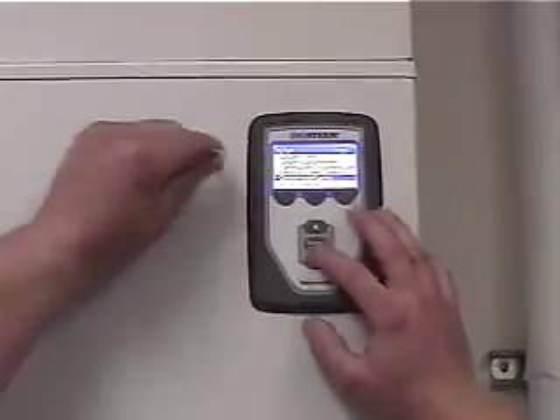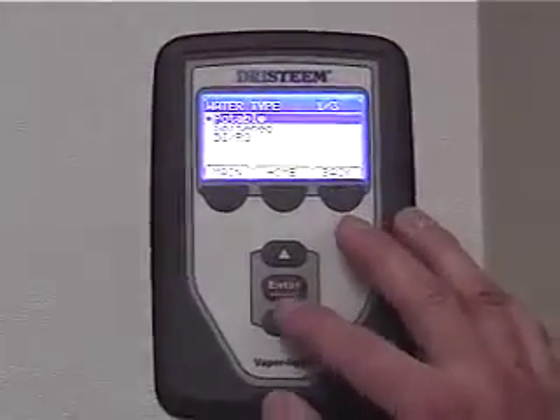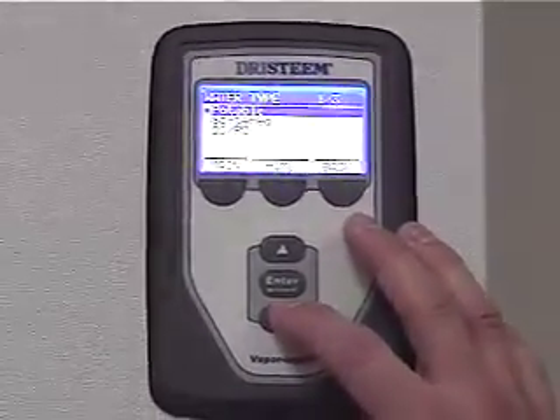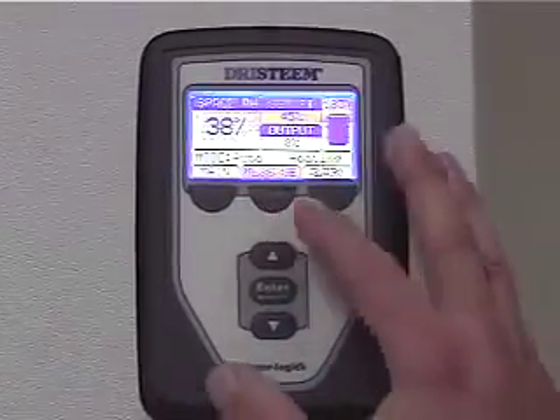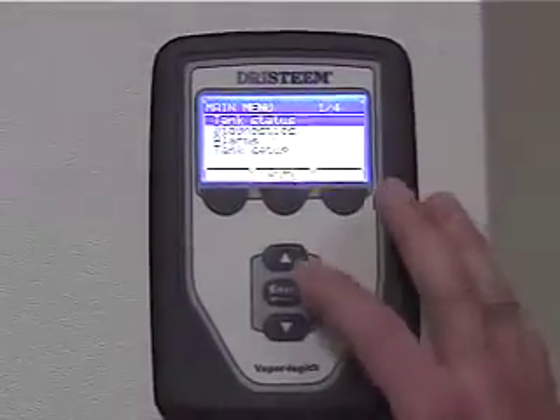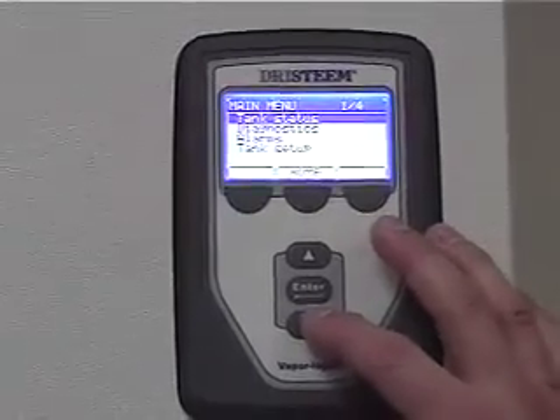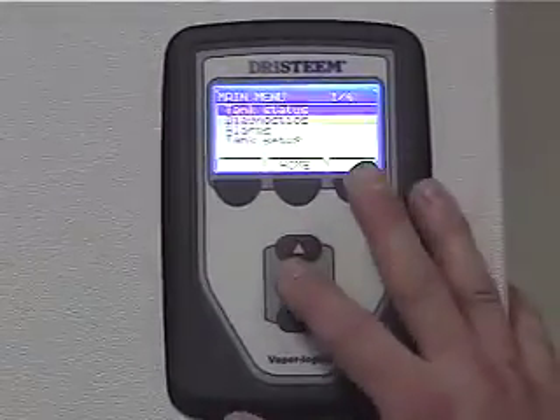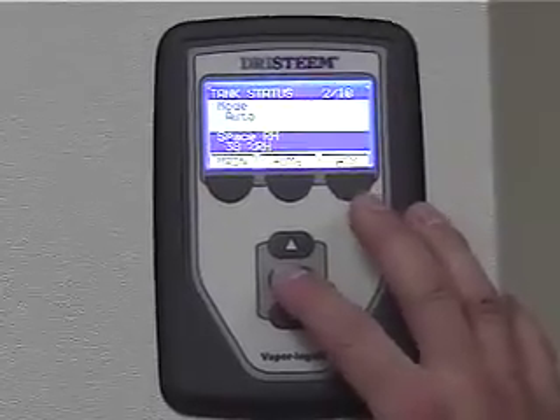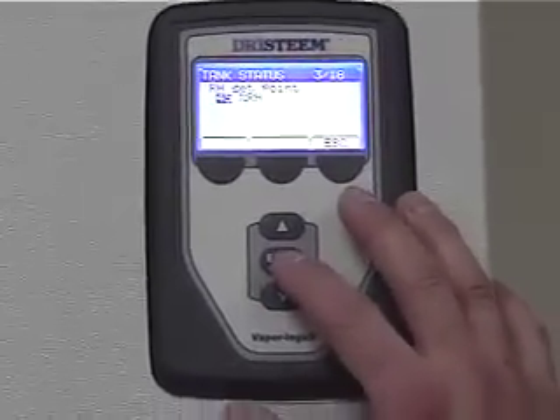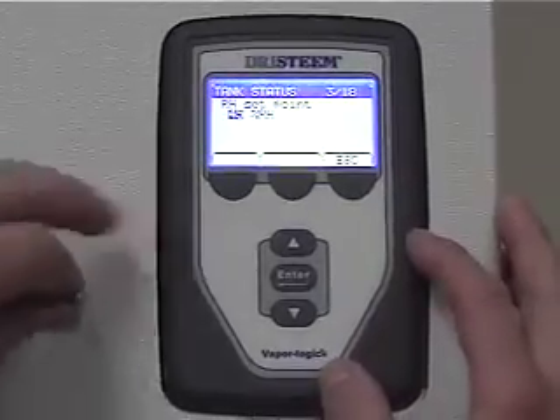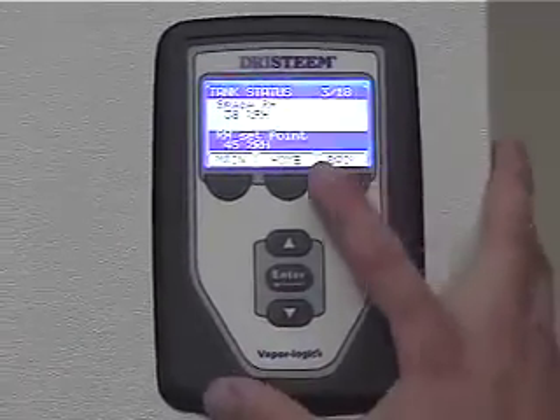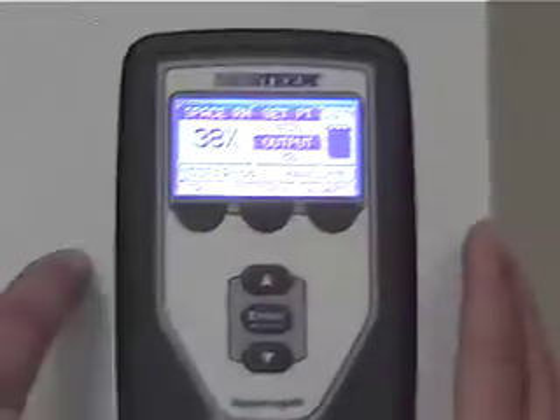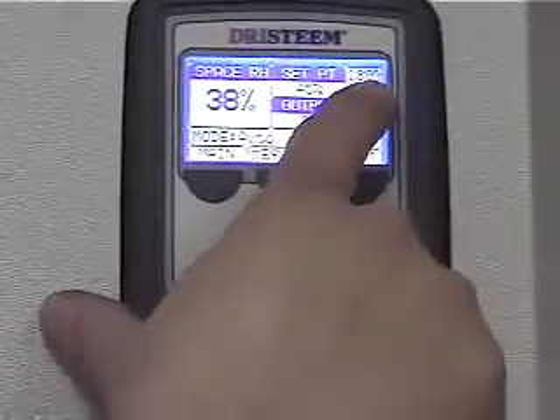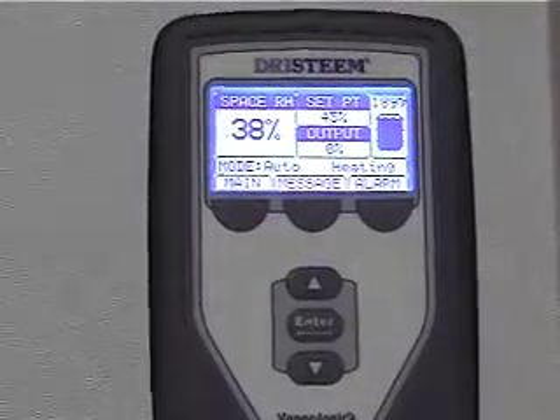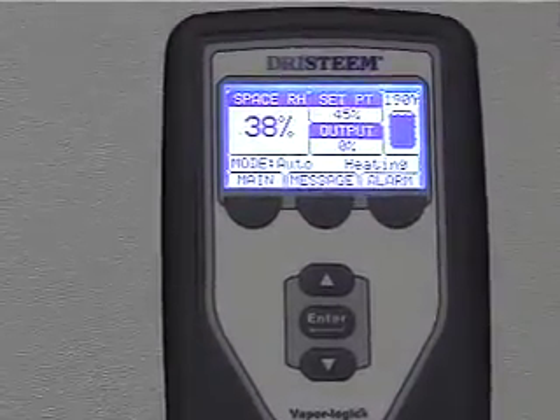So see, you can go in here and you can put in the water type you have, whether you have soft water, whether you're using deionized water, whether you use the softened water. Everything in these is programmed. Hey, you better change the relative humidity. Tank status. Go down. Go down another one. Right there. See, if you go back to the home, so escape, get out of here. You're going to see here in just a second. Yeah, you just need the home. You're going to see here now that it's finally full of water. Our temperature's climbing. So here in just a minute, it's going to start telling you the output of steam it's putting out.